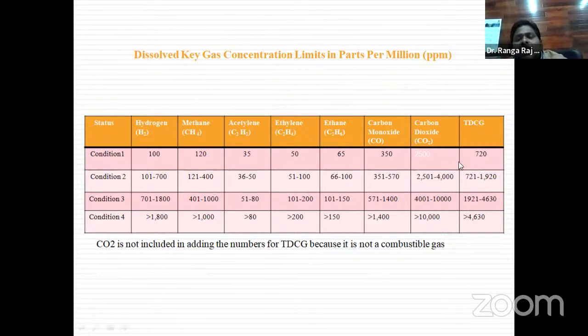If the sum is less than 720, the oil condition is excellent. If it's between 721 and 1920, it is good or moderate. If it's between 1921 and 4630, it is poor or low moderate. If it is more than 4630, that is the worst case, and we have to replace the oil with new oil.